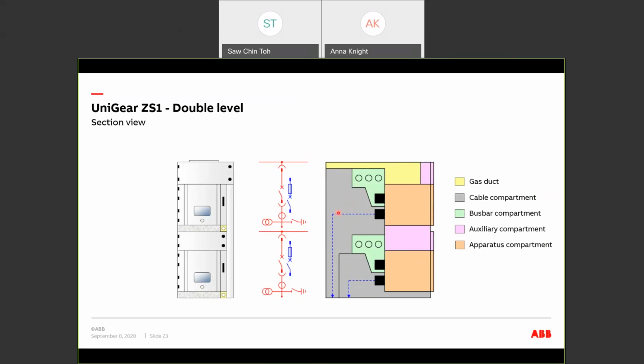The cubicle will have 2 sets of busbar compartments as well as 2 sets of cable compartments. So for this type of panel, the cable termination will be done from the back of the cubicles. So we need to allow some space at the back of the switchboard for the cable termination.